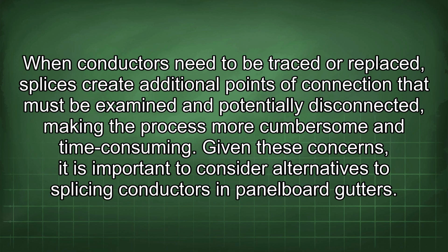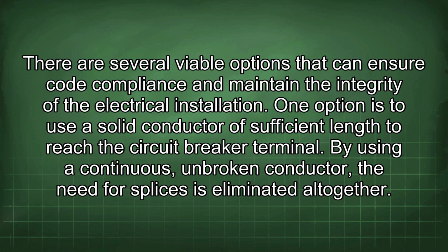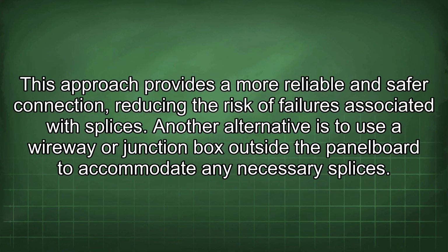Given these concerns, it is important to consider alternatives to splicing conductors in panelboard gutters. There are several viable options that can ensure code compliance and maintain the integrity of the electrical installation. One option is to use a solid conductor of sufficient length to reach the circuit breaker terminal. By using a continuous unbroken conductor, the need for splices is eliminated altogether. This approach provides a more reliable and safer connection, reducing the risk of failures associated with splices.